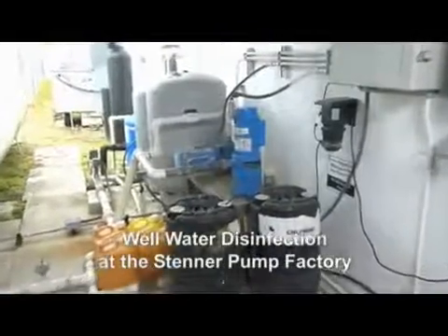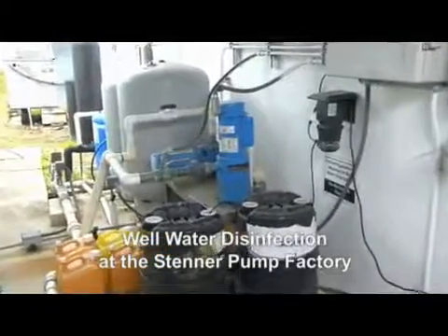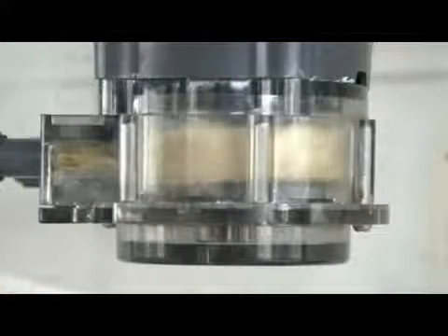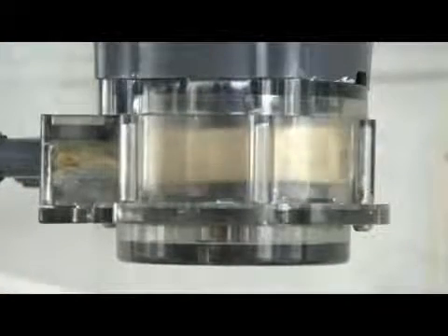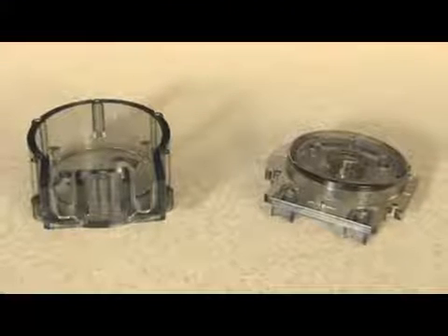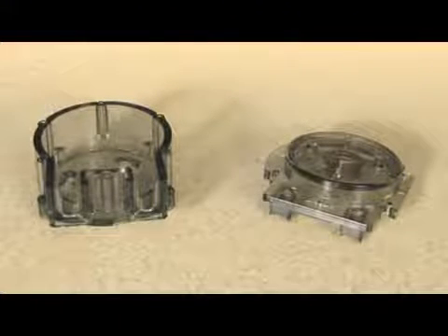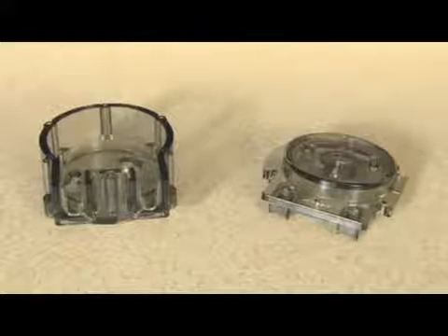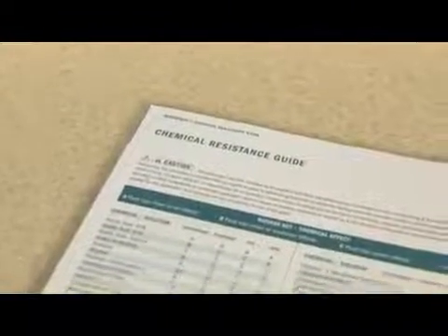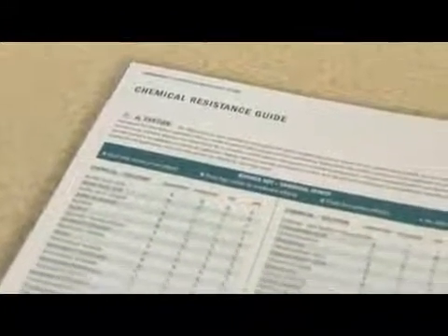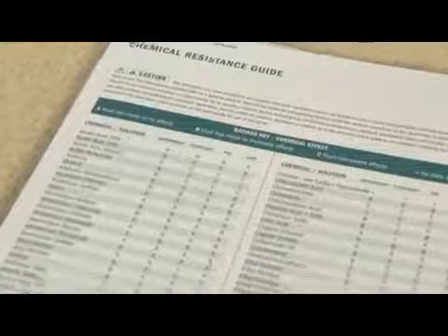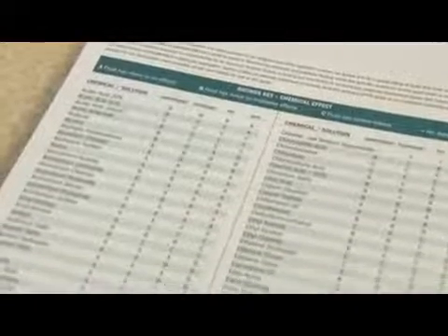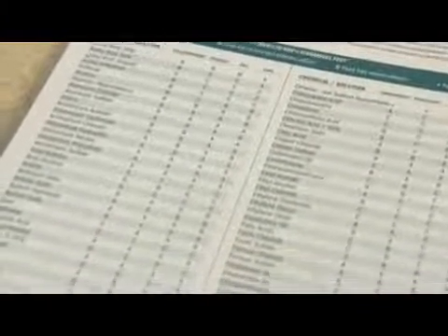Corrosive chemical fumes or chemicals that collect on the roller bushings from a tube leak can result in seizing the rollers in the roller assembly. A new pump tube will perform poorly if the rollers are seized. Long-term chemical exposure can cause the tube housing to crack if the chemical is not compatible with the polycarbonate plastic. The solutions being pumped should be referenced with Stenner's Chemical Resistance Guide for the pump tube and tube housing material. The Chemical Resistance Guide can be found in the catalog or on the website.